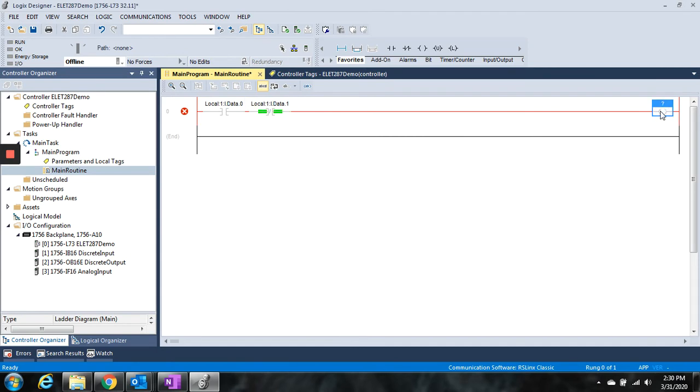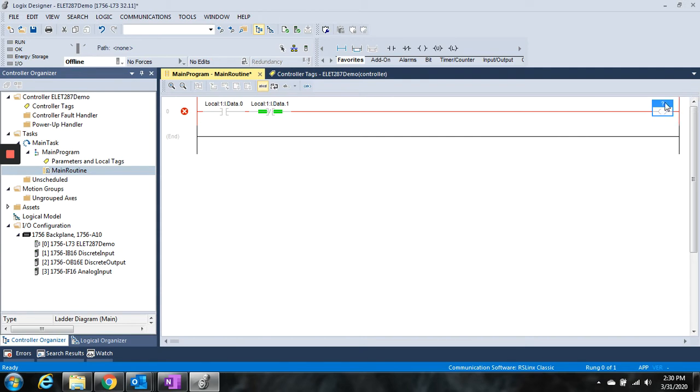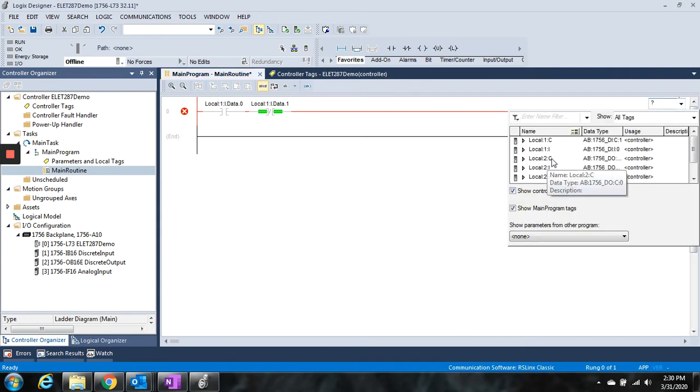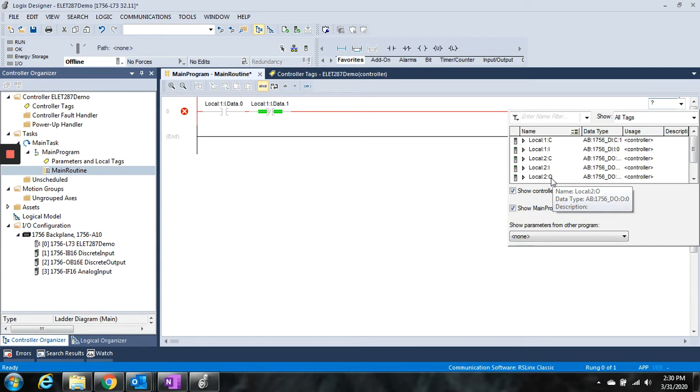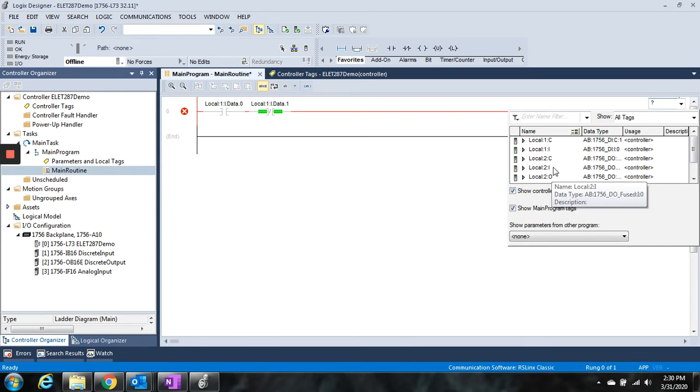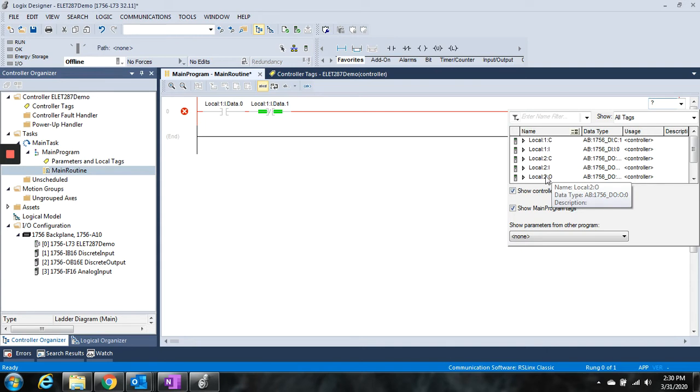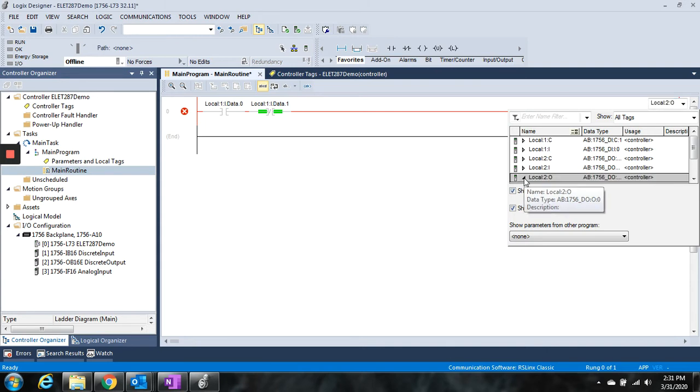Then if we want to tie this coil to an actual output, we're going to use the output card. The output card is in slot 2, as we see right there. So we're going to double-click, we will go to our table here, and we're going to go local 2. Now, since this is an output, we're going to choose the O. Since this output card can have some diagnostic data to it, they tend to use the I for the diagnostics and O for the actual outputs themselves.